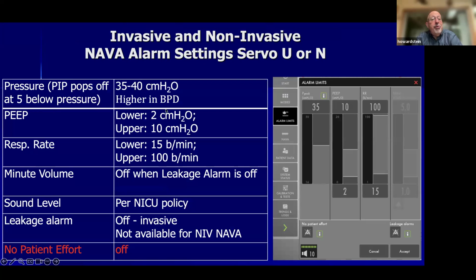These alarms are very important. We set that pressure alarm at 35 to 40. The PEEP, respiratory rate, minute volume, and sound level alarms are pretty much routine NICU policy, and we would suggest following it. But the other 2 alarms are very important, and one is this leakage alarm.